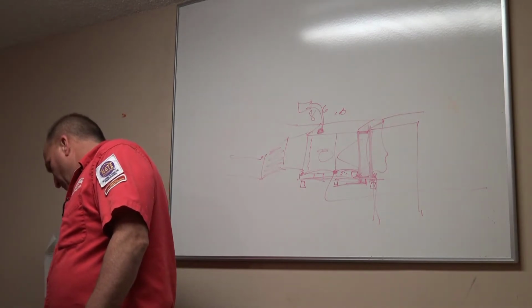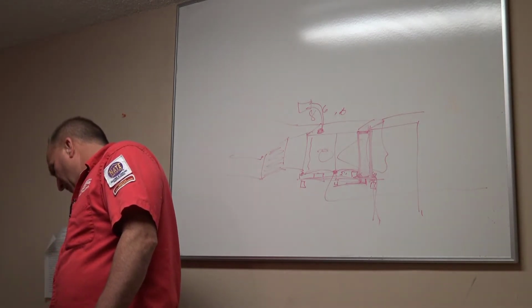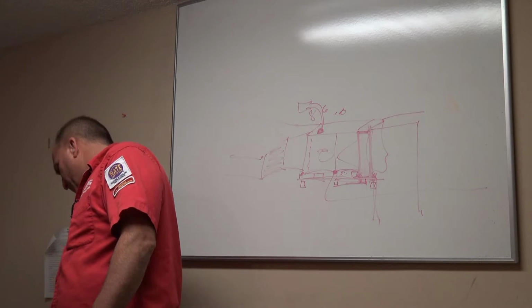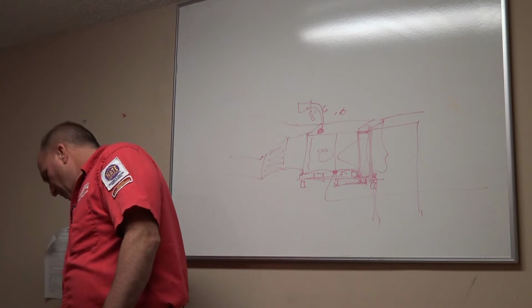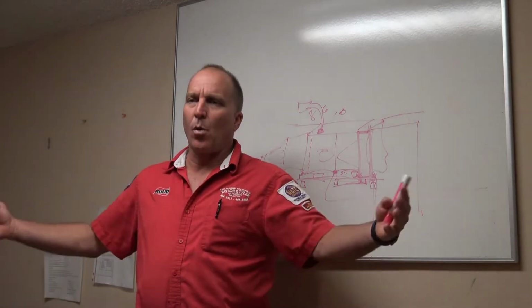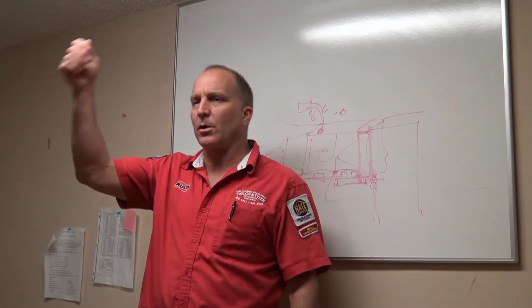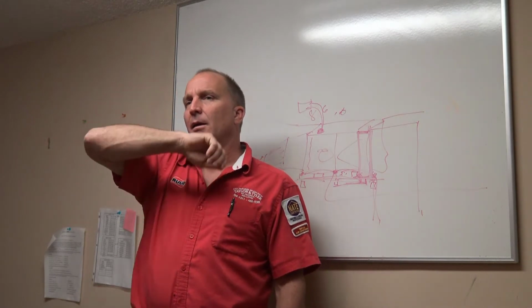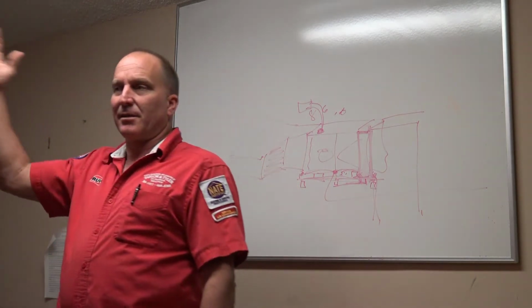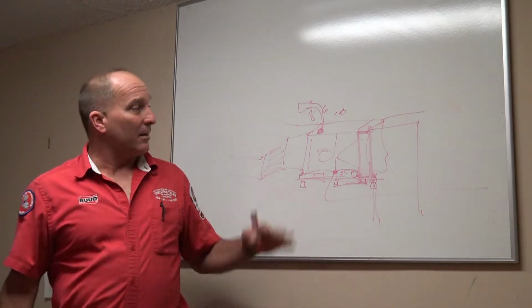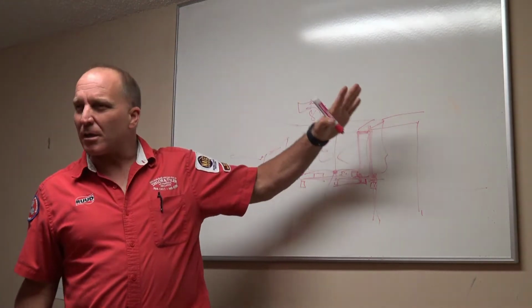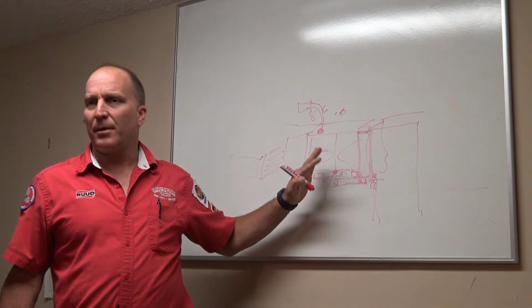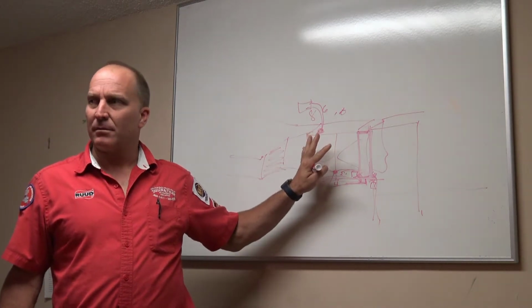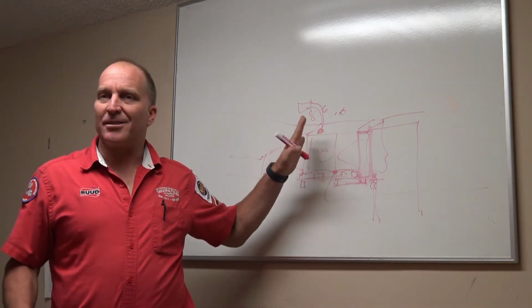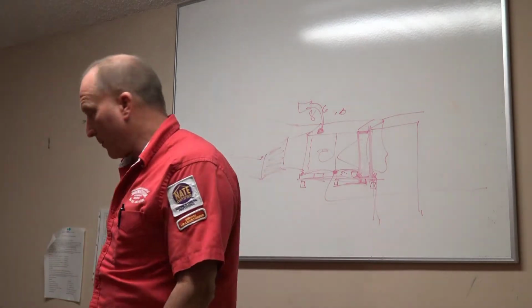The air handler is rusted, doors don't fit properly, electrical is not secured with the Romex connector, supply is blocked off, platform is rotted, can't service system because the space is unsafe. That's poor. That's what I'm telling you. If it says poor, what should be your recommendation? Change out the air handler. Change out the air handler or replace the entire system. Or it could be the installation is completely poor, but the actual air handler is 2 years old. Then your recommendation would be reinstall the air handler properly. Okay?